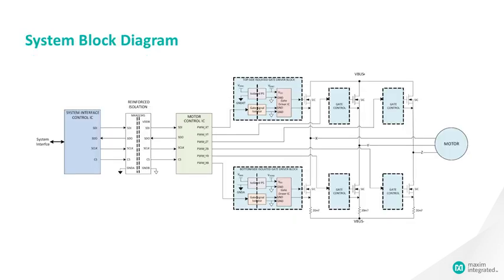So here is a system block diagram showing an industrial AC motor drive application. 3-phase motor voltages and rectified bus voltages are dangerously high, and they need to be isolated from the system interface for safety reasons. Here are reinforced isolators. MAX22345 can be used to isolate the system interface side from the high voltage side. In case the motor accidentally shorts to the control circuits, the dangerously high voltages would be blocked by the isolation barrier and prevented from reaching the human operators.